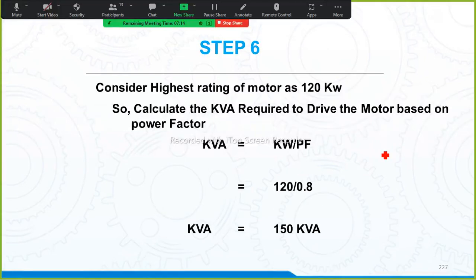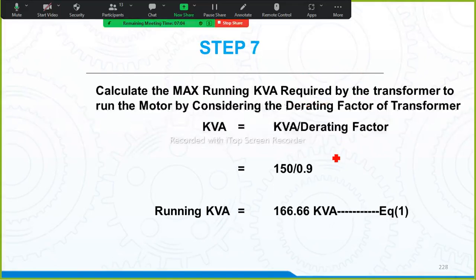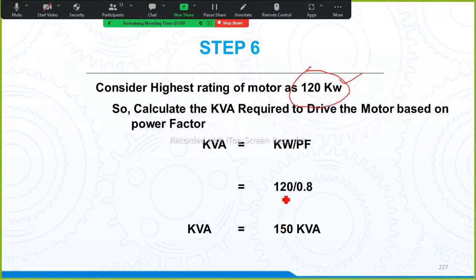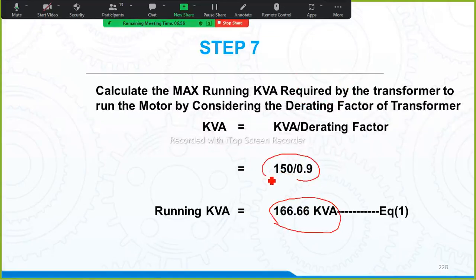The maximum running kVA required to drive this 120 kilowatt motor is 166.66 kVA. How did we calculate it? First we considered the power factor, second we considered the efficiency of the transformer, and we got 166.66 kVA.